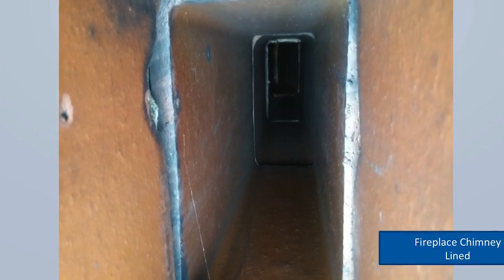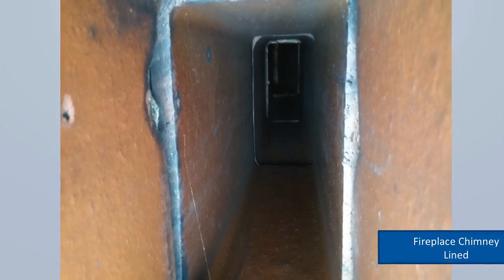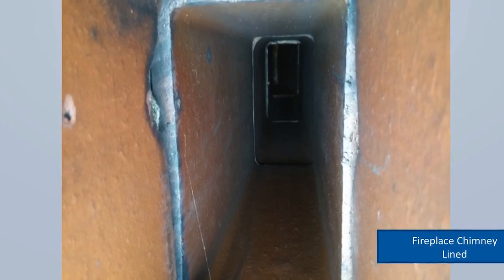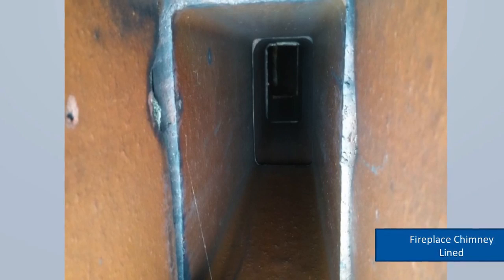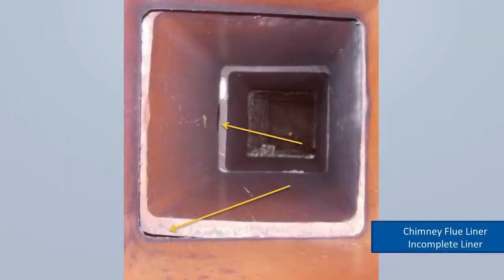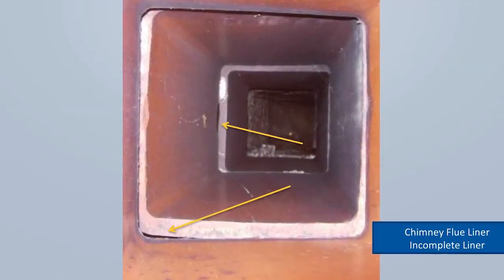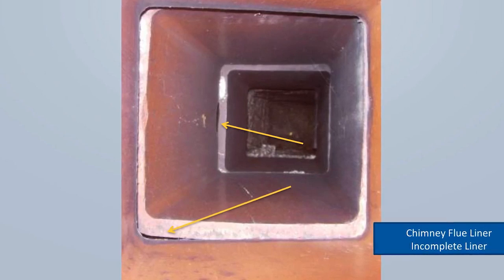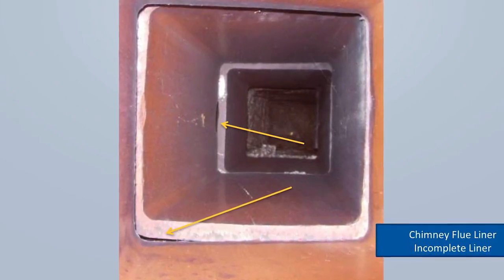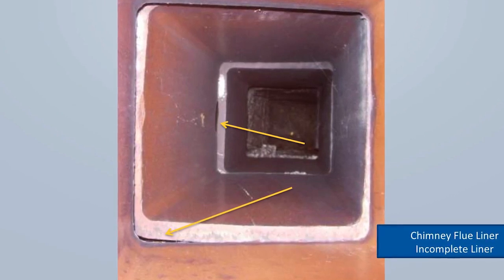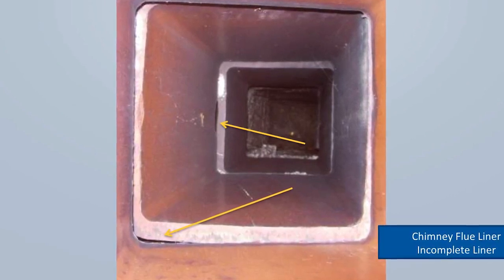So what you want to do is see if you can look down that flue and see if there's any cracks, spalling, deterioration. Sometimes multiple pieces are put together to create an entire flue. Look for mortar joints in those connections that might be gone or cracked and leaking.